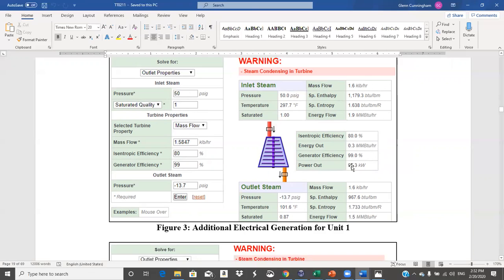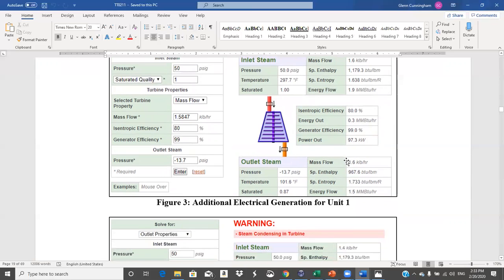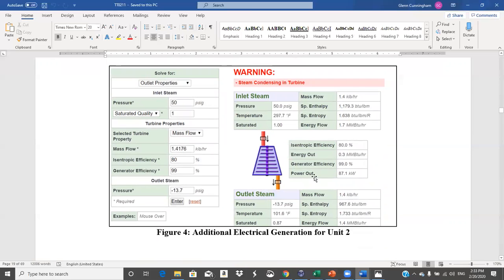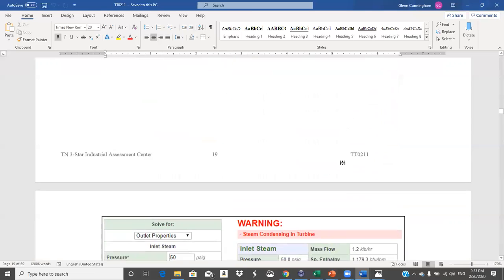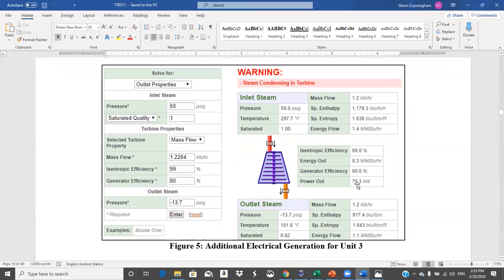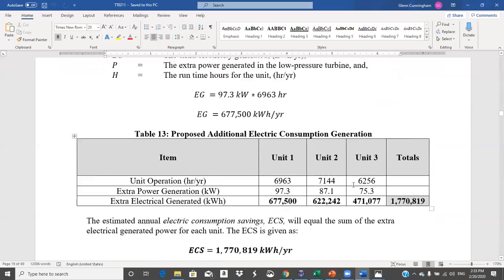So this is just the increase in mass flow based on recovery of the blowdown flash steam. We're going to put this much more steam through the big turbine. We didn't do the whole thing, we just did the increase to see what power that would get. And that's 97.3 kW. Oh shoot, that's worth having. So that's for number one. Unit number two came out 87.1, and unit number three came out 75.3. Then you estimate how many hours per year this is going to happen, and put all this together in a nice report. But that's the fundamental engineering behind the recommendation.